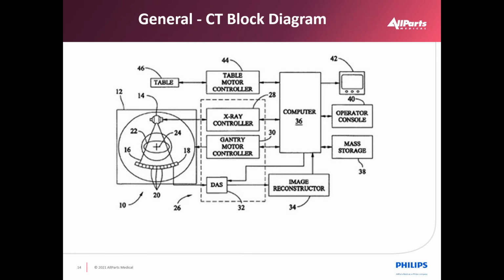When we say high voltage, we're dealing with up to 140,000 volts in conventional CT. Sometimes we'll have a negative 70,000 volts on the cathode side and a positive 70,000 volts on the anode side. So our total potential is 140,000 volts. CT scanners will go down to 80,000 volts, 80 kV.